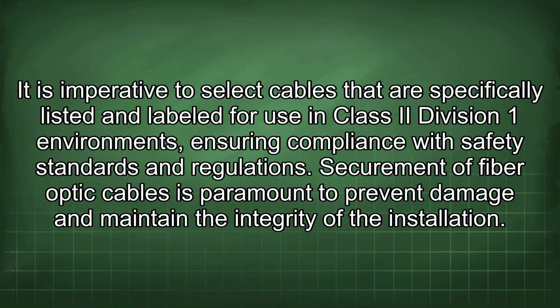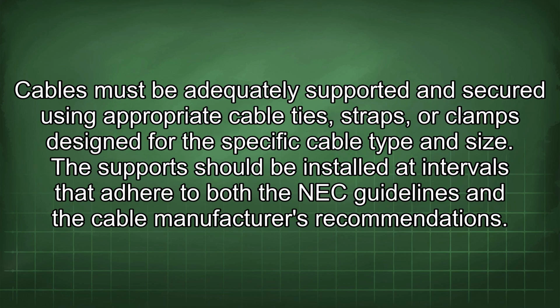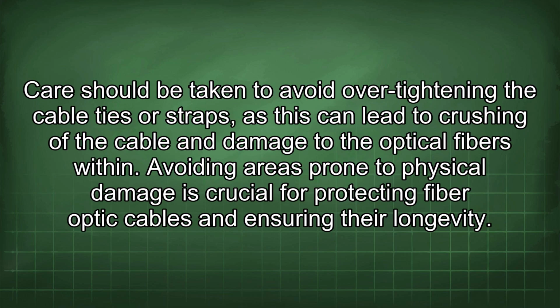Securement of fiber optic cables is paramount to prevent damage and maintain the integrity of the installation. Cables must be adequately supported and secured using appropriate cable ties, straps, or clamps designed for the specific cable type and size. The support should be installed at intervals that adhere to both the NEC guidelines and the cable manufacturer's recommendations. Care should be taken to avoid over-tightening the cable ties or straps, as this can lead to crushing of the cable and damage to the optical fibers within.